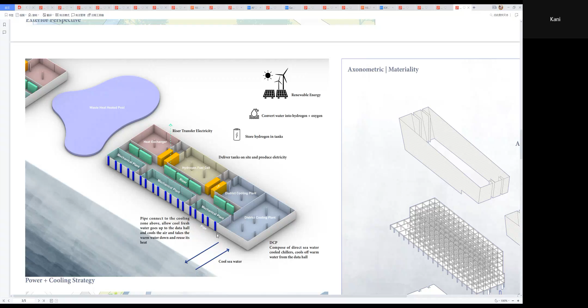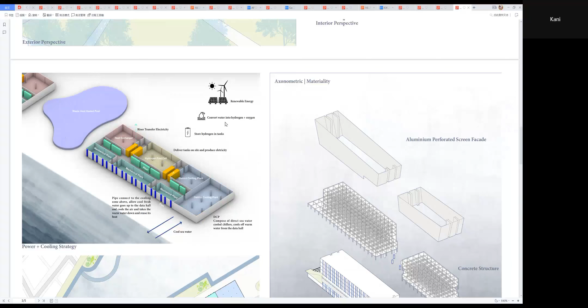For the cooling strategy, I'm using district cooling plants, composed of direct seawater-cooled chillers that cool the warm water from the data hall. These pipes connect to the cooling zone above, allowing cold fresh water to go up to the data hall and cool the air, taking the warm water down and reusing its heat for the waste-heated pool.